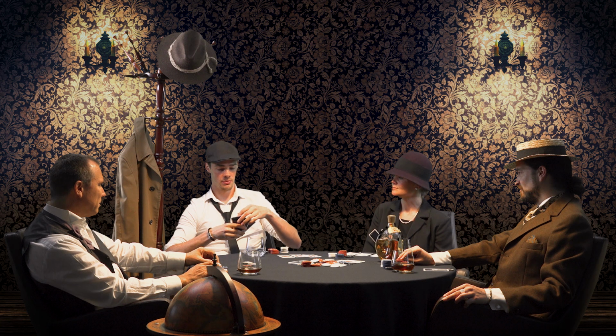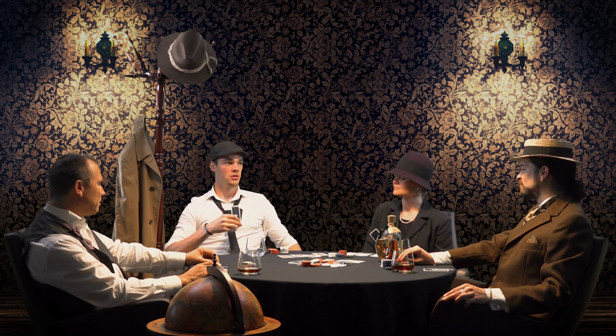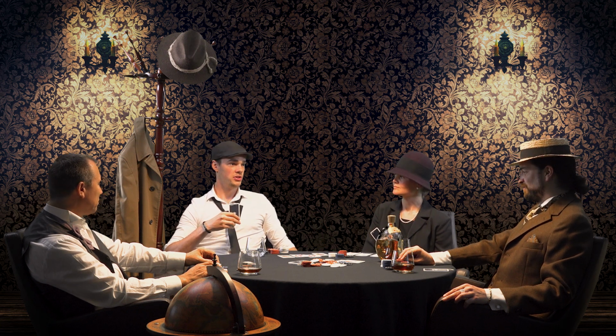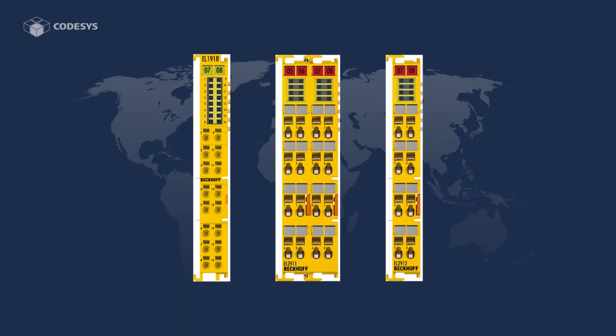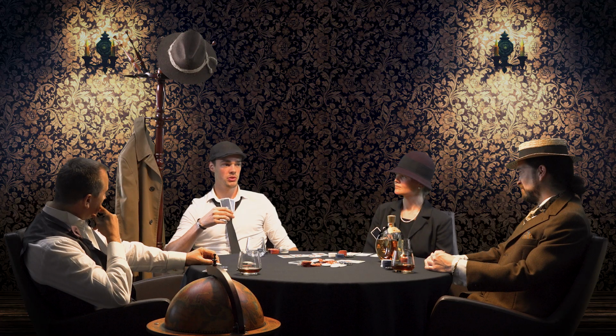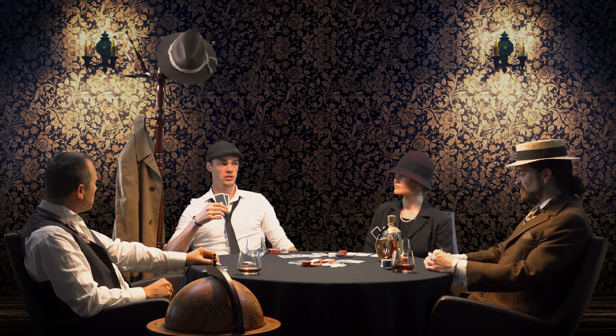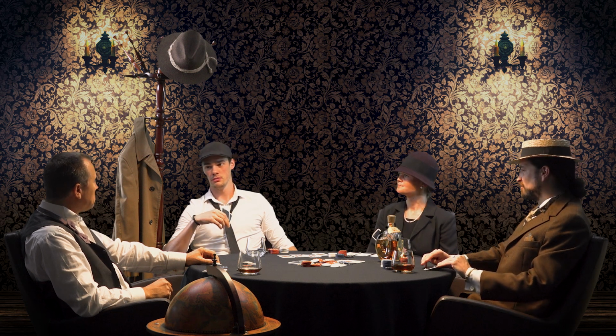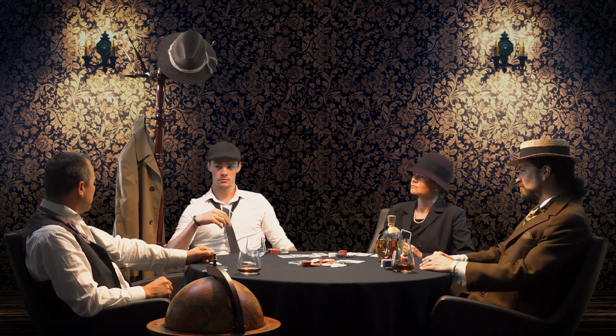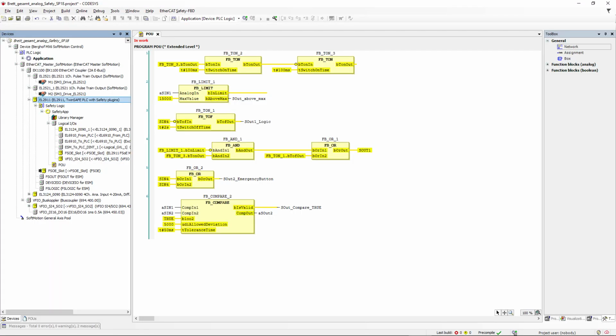Speaking of which, my second Fieldbus card is the newly supported EtherCAT safety modules. They save even more time and money, in the software through engineering directly in CODESYS, but also on the hardware, because these modules already have integrated safety IOs. This means simple application programming in the CODESYS project and no additional mechanical effort. And if I need more IOs, then they're installed on the module? But of course, you can also couple additional safety IOs, just as before.